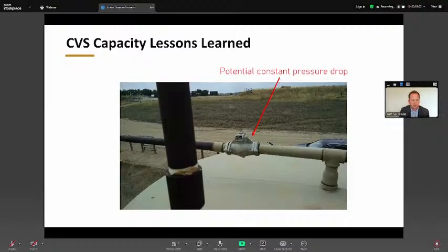So as we go through this, there's tons of lessons learned that you want to take into account as you're designing a closed vent system and looking for systems or components that cause significant pressure drop for the vent system. So these are little Enardo 800 series inline vents, so it's got a weight on it and it allows flow. Well, these have extremely high pressure drop. Those tend to be, for a 4-inch, about 300 equivalent feet of 3-inch piping.